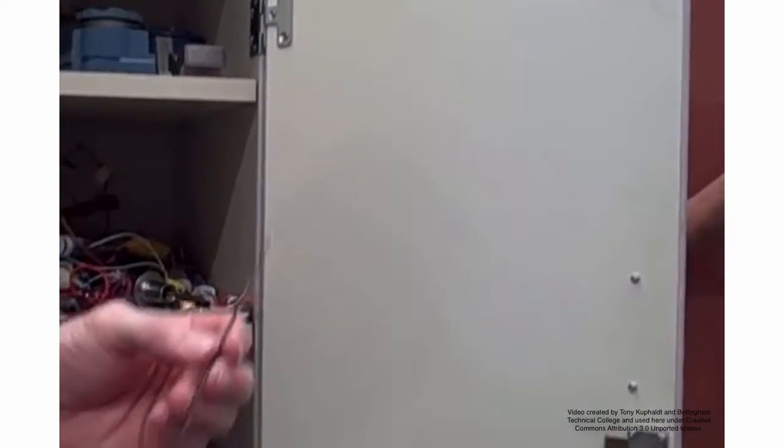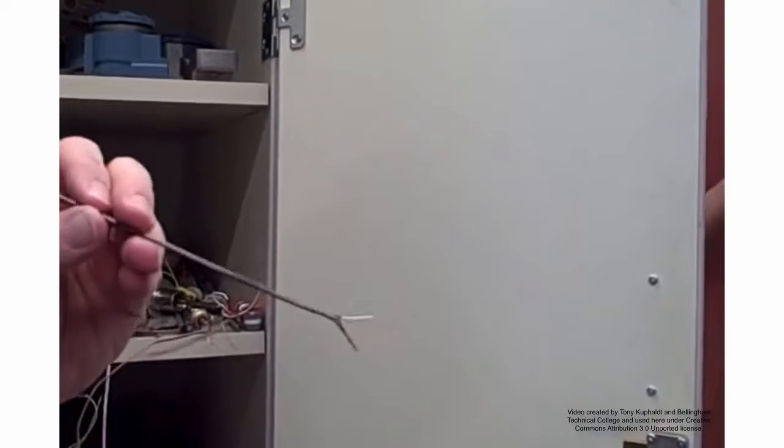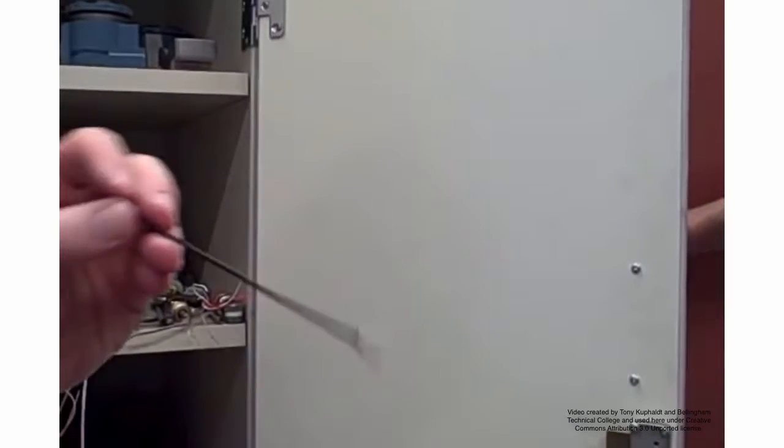What we're looking at here is a piece of thermocouple wire. This right here is type J. We can tell that from the color code, white and red, with red being negative and white being positive.